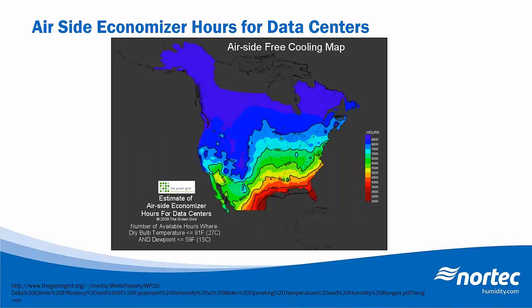The second is economization over a slightly wider temperature range where there may be an increase in temperature for a short period of time. This method allows operators to take advantage of more hours of economization. And the third that we'll look at is a chillerless facility where the data center temperature is higher and will vary over a wide range depending on what the outside air conditions are. In this case, facilities may use supplemental cooling methods like evaporative cooling.